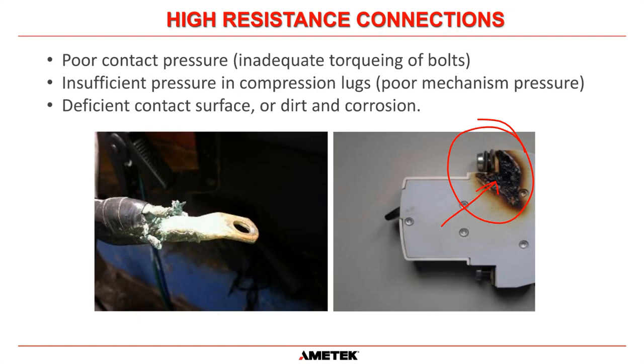And eventually that could have gone on fire, maybe this did go on fire, which is definitely a situation we want to stay away from, because if it's in a room that has fire suppression systems, that's going to go off. It's going to do whatever it needs to do, whether it's foam or a halon system. You don't want smoke in your electronic equipment. So high resistance connections and deficient contact surfaces are something that you have to be very, very aware of.